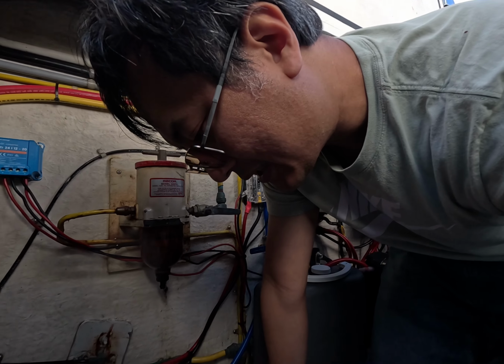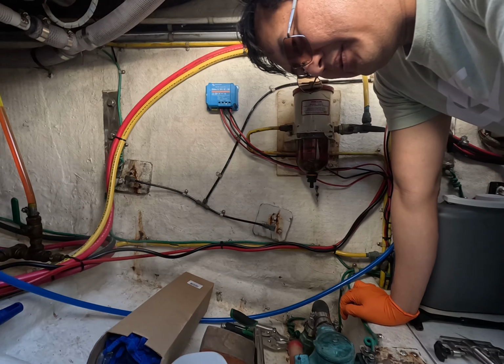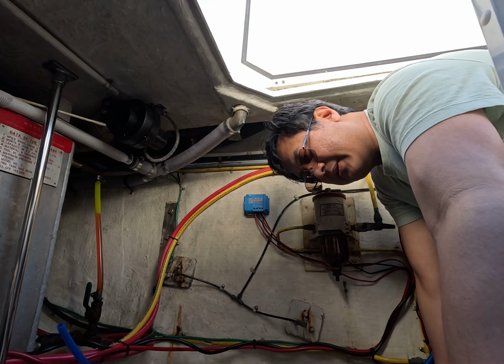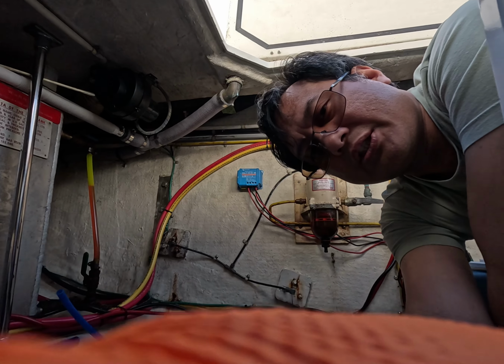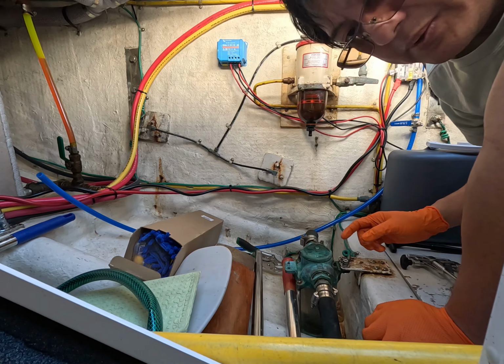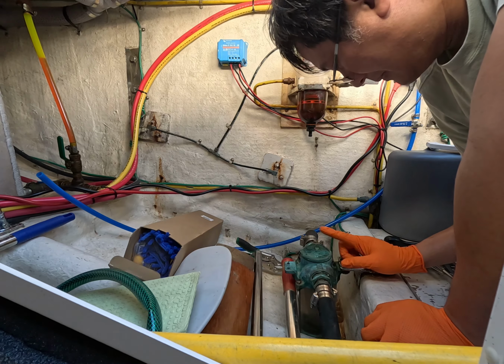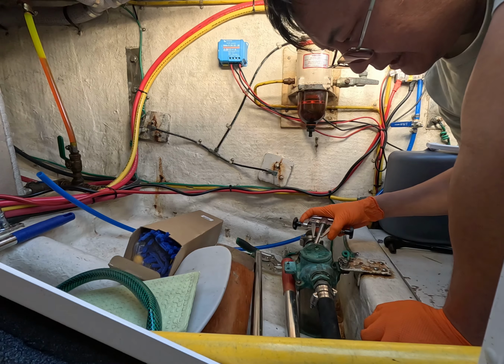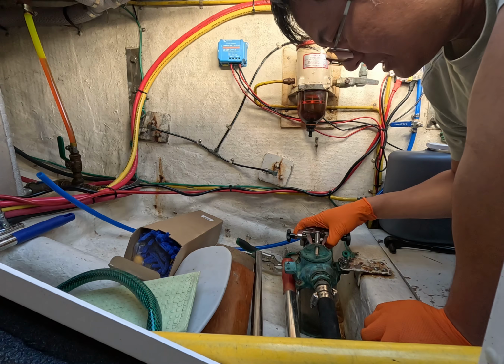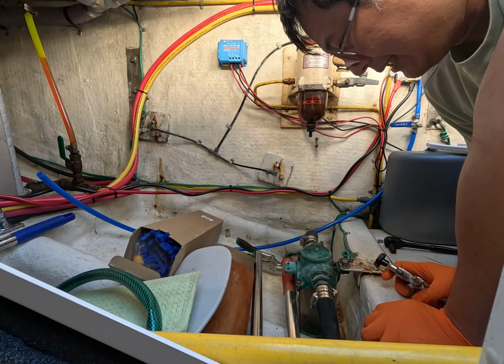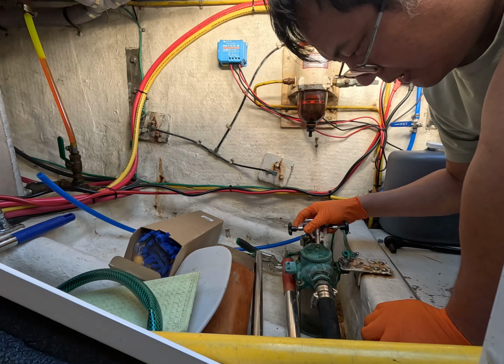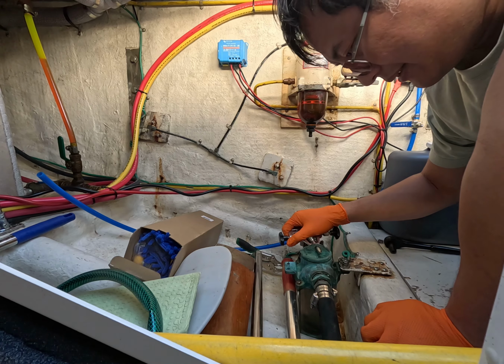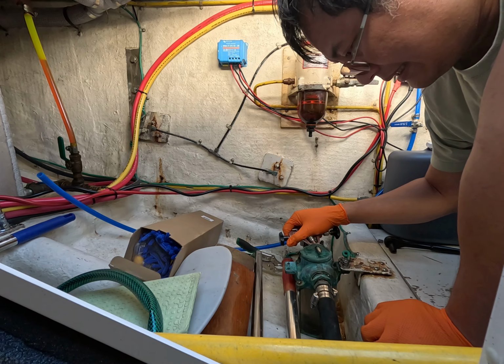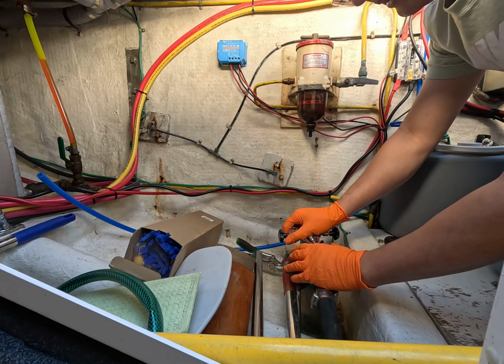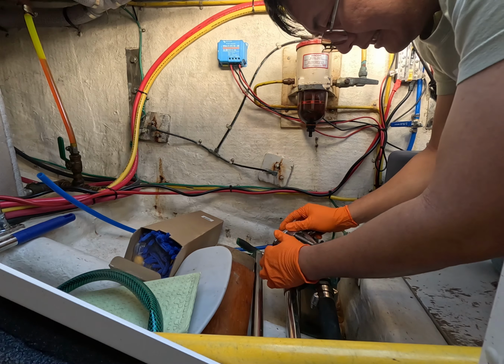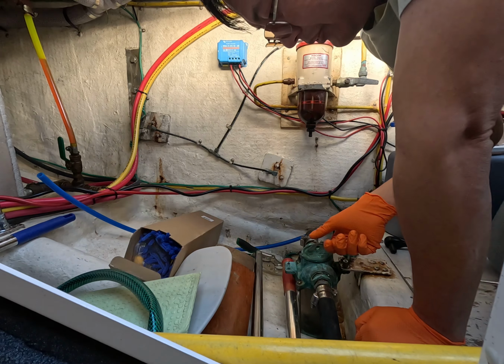One more thing I like to do before I close shop for the day is, since we have a lot of solar, we don't typically need the genset all that much. In fact, it's kind of redundant at this point. But in order to store it for long term, I like to flush the genset so the cooling system and the heat exchanger aren't full of salt water, which among other things causes corrosion - some of it galvanic, so any stray current will conduct through that salt or brine water.